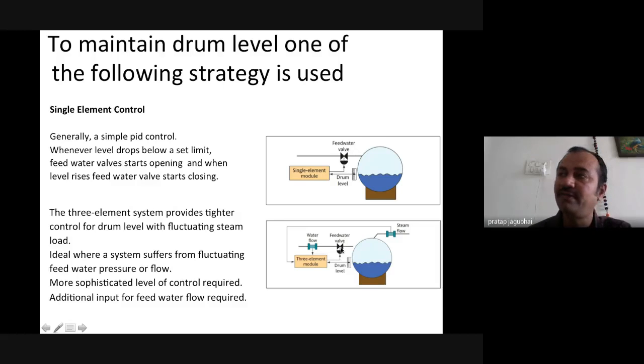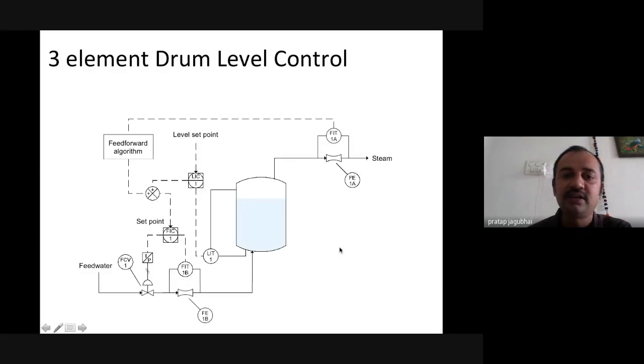If we give the control element the desired action, the set point will be achieved in a good manner, and we can have a desired response. So in the P&ID diagram, we can see in more detail where steam flow is getting sensed by the flow meter.